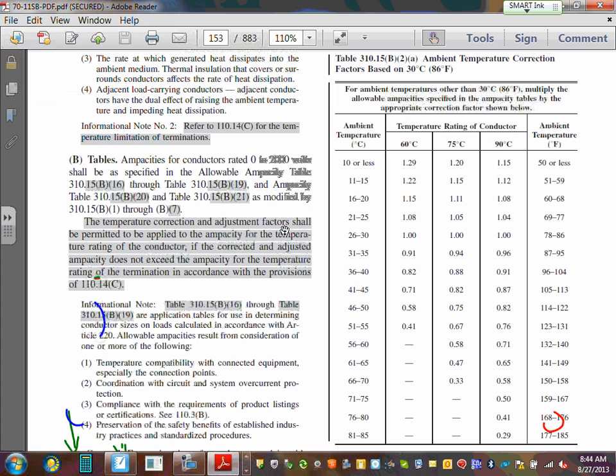Okay, so here's one more table you must know if you're in the electrical industry. This is table 310.15(B)(2)(a), ambient temperature. So, Adam, if the ambient temperature of your conduits here is other than 30, you have to derate. That's it. And typically when we derate, Matthew, we derate if the temperature is higher, because higher is worse. Lower is not a big deal, but higher is worse.